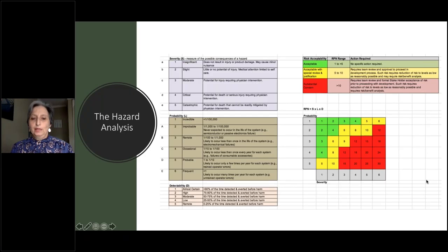And then lastly, the detectability. If you can actually tell that there's a problem, then you can set off alarms, you can have a test result that says test failed, for instance. So that's a good thing. If it's detectable, it's positive. If it's not, then you might get this false negative, false positive, or just not know that a ventilator, for instance, has ceased to function. You take these numbers and you multiply them out.